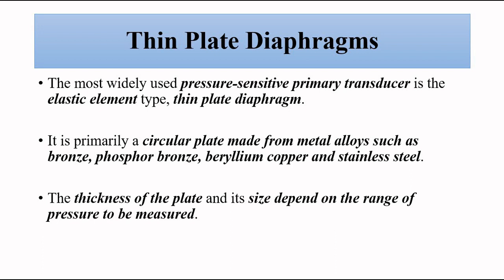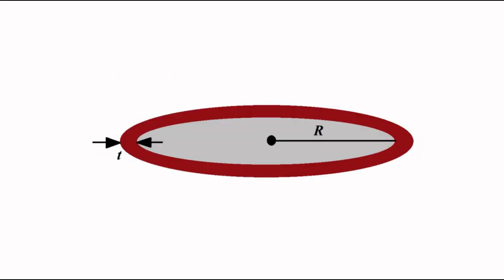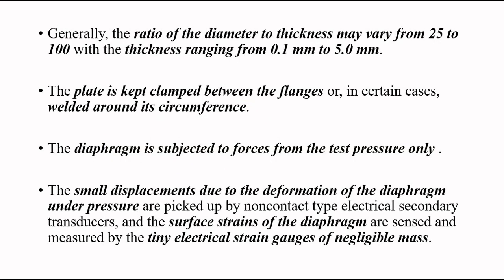So this is the general structure of a thin plate diaphragm. It's circular shaped with a certain thickness T and radius R. Material selection, radius, thickness all depend on the range of pressure that has to be measured. Certain things have to be taken care of while designing thin plate diaphragms, which is the ratio of the diameter to thickness. It may vary from 25 to 100, with thickness ranging from 0.1 millimeter to 5 millimeter.